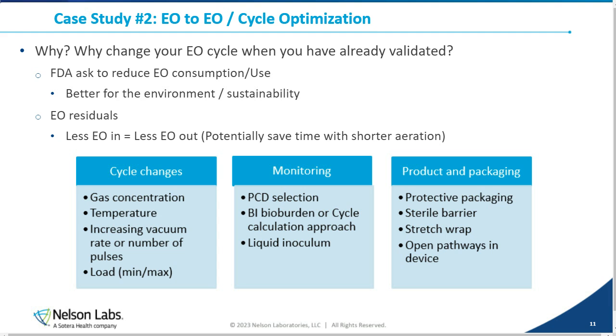I'm also going to potentially look at how my monitoring is performed. I have a process challenge device, a PCD, that tends to be a worst case setup. Well, have I made it too worst case, so much so that it's no longer representative? Also adjusting my biological indicator, the newer BI bioburden based, so I adjust my BI to be more reflective of my product bioburden, as well as liquid inoculum. It tends to be a little bit better carrier.